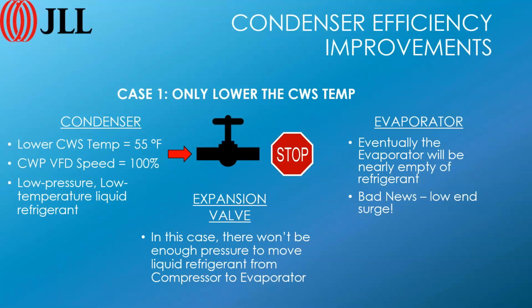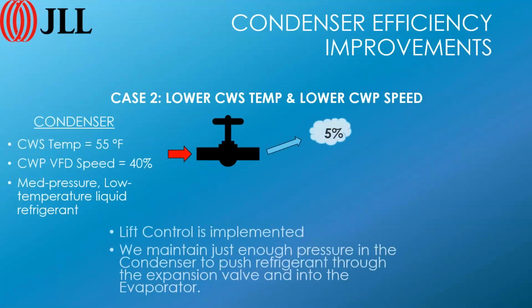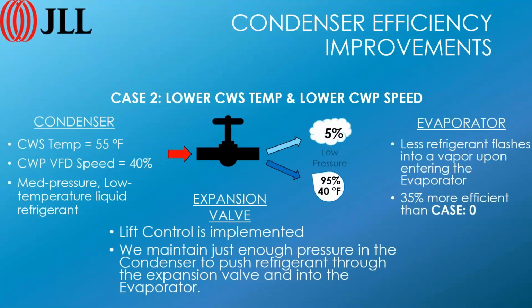So what we do is we still have that temperature going in, we still get the condenser water temperature cooler, we slow the pump down, and now instead of losing 30% of our gas, flash gas, we're losing about 5%. So that's how we get a chiller that's a 1,000-ton chiller running at 1,300 tons. We get some extra capacity out of it because it's a little bit cooler.